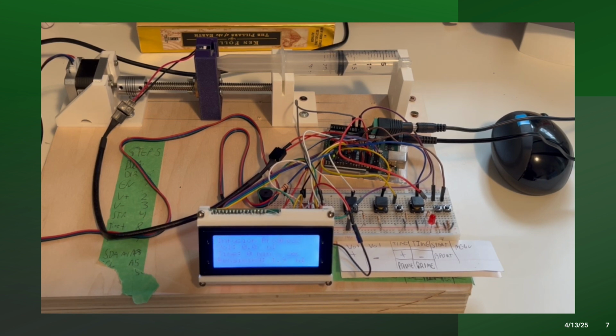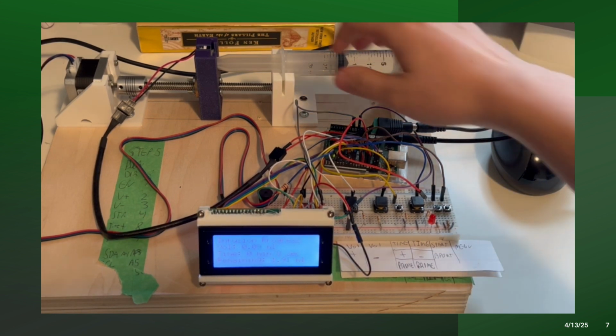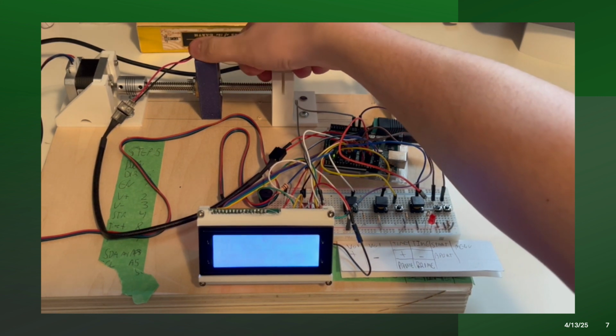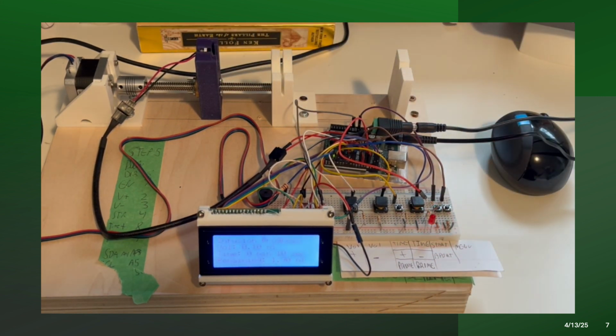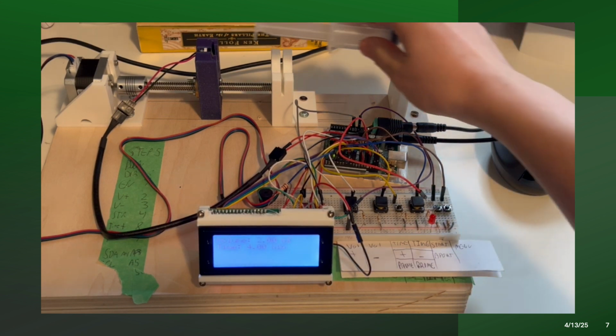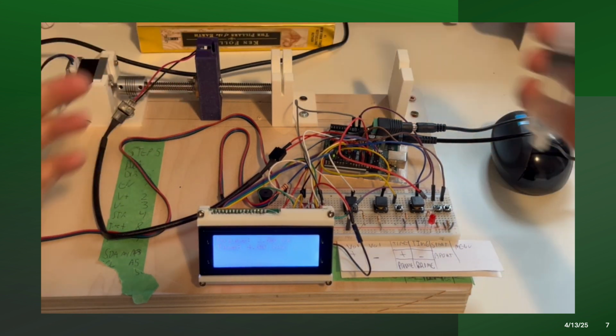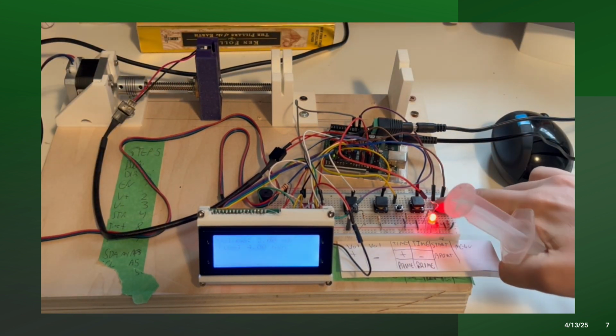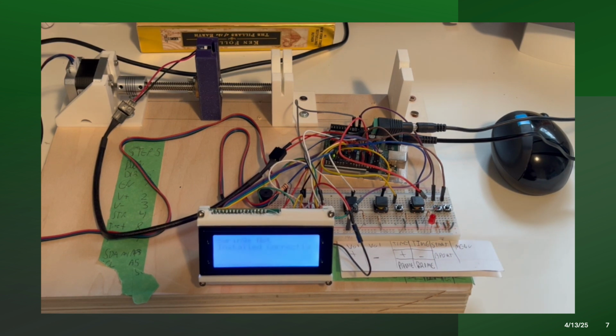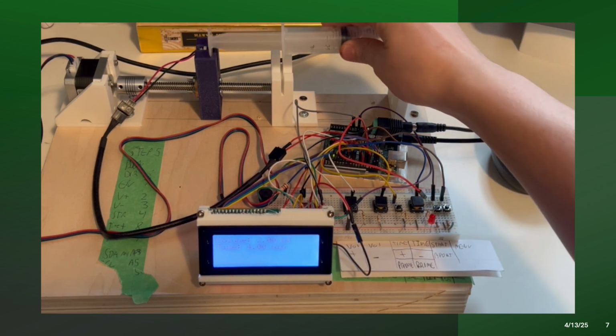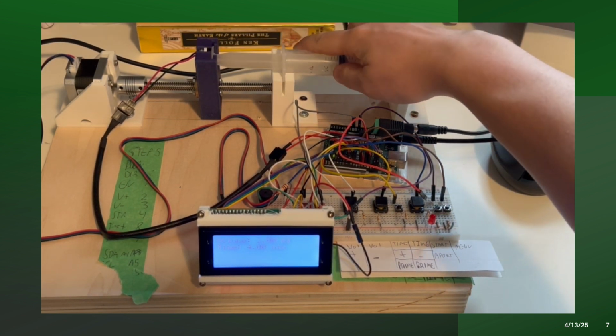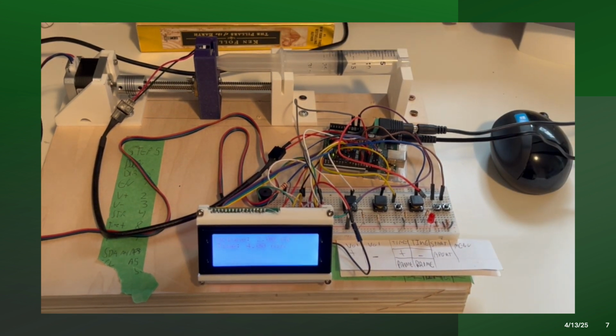Another little thing that we've included is a security alarm. So if for some reason the syringe gets removed prematurely, which would be dangerous, it'll abort the infusion and give a sound notification. Additionally, if you try to start an infusion without the syringe inserted, you'll get that same alarm notification. So that's just some base functionality of this syringe pump, just for reference and for a visual component.